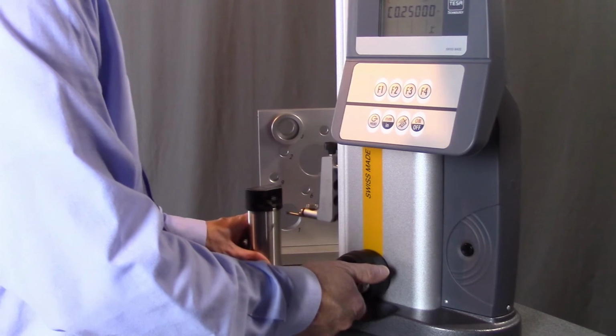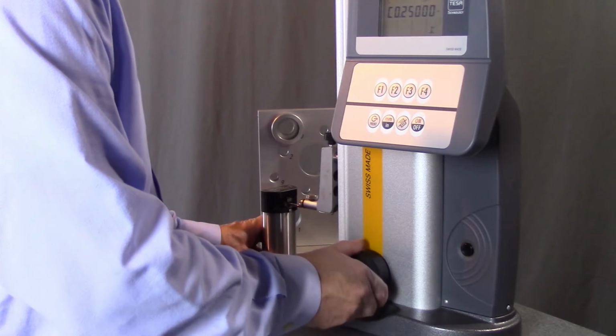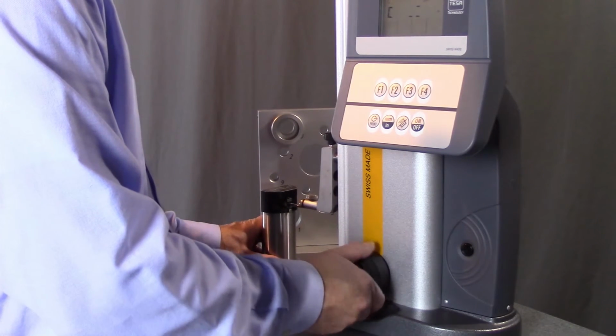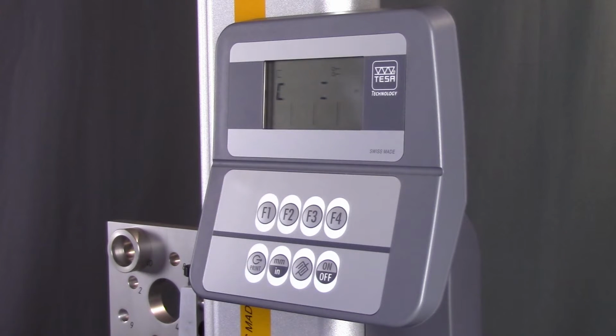It doesn't matter if you start by making contact on the top or the bottom, but you will take 4 hits with the probe on the setting master. When you're finished, the display reads Start 2 and the gauge is ready to measure.